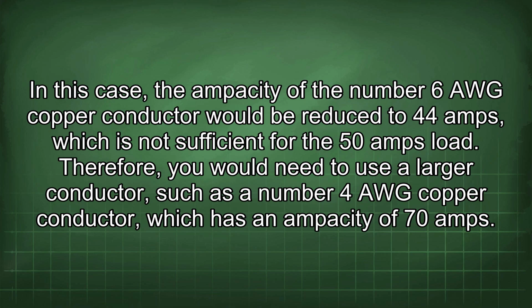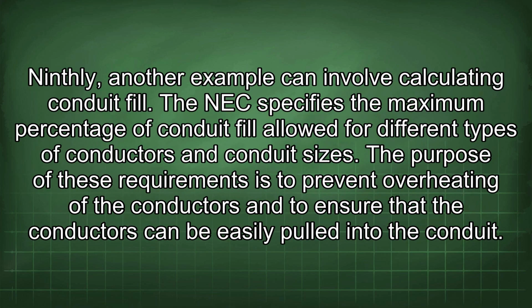Therefore, you would need to use a larger conductor, such as a number 4 AWG copper conductor, which has an ampacity of 70 amps. Ninthly, another example can involve calculating conduit fill. The NEC specifies the maximum percentage of conduit fill allowed for different types of conductors and conduit sizes. The purpose of these requirements is to prevent overheating of the conductors and to ensure that the conductors can be easily pulled into the conduit.